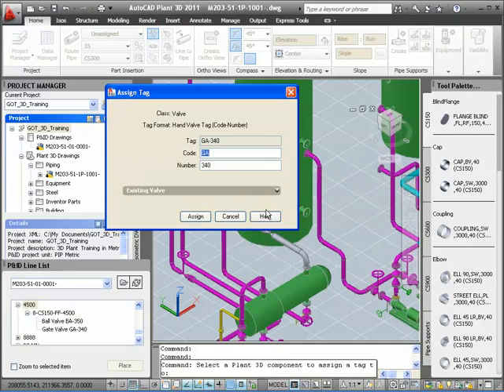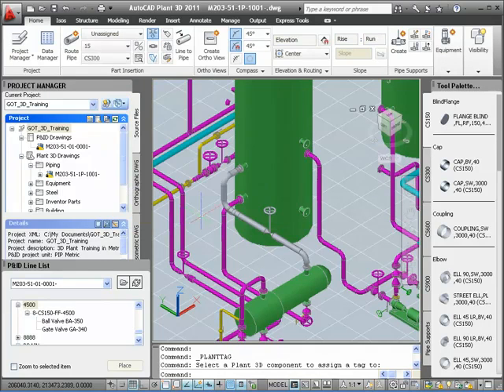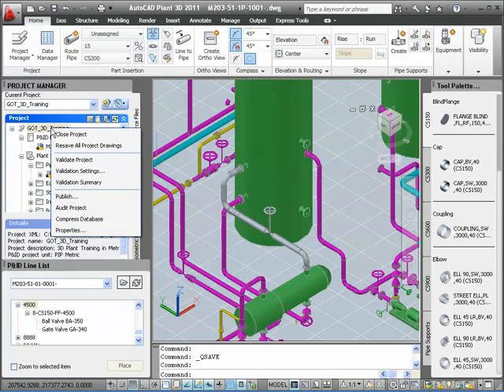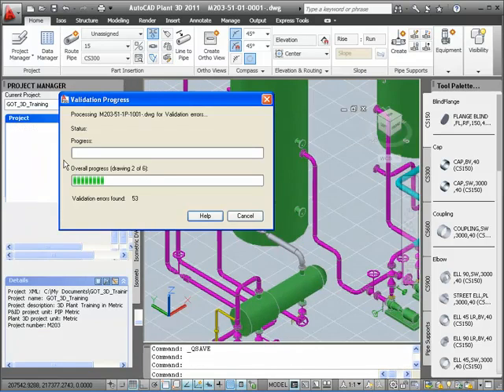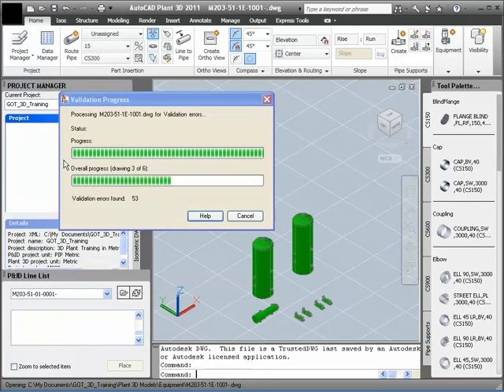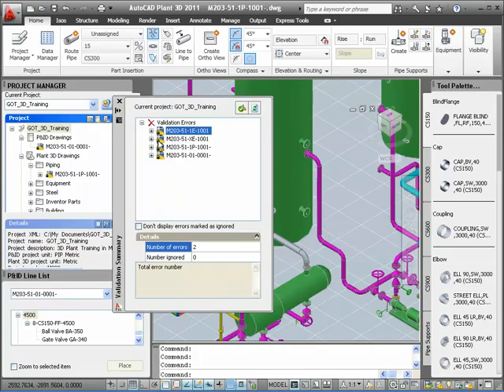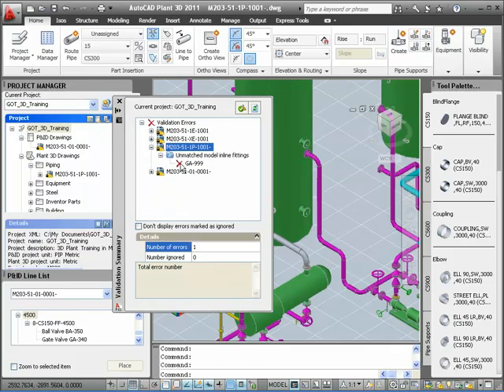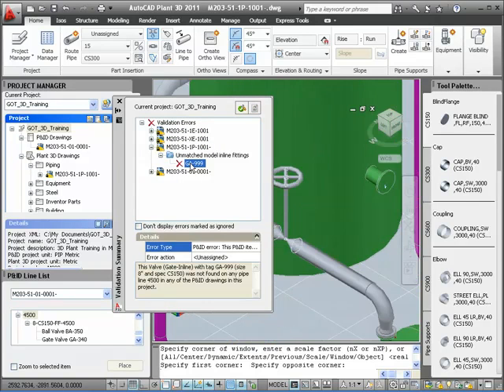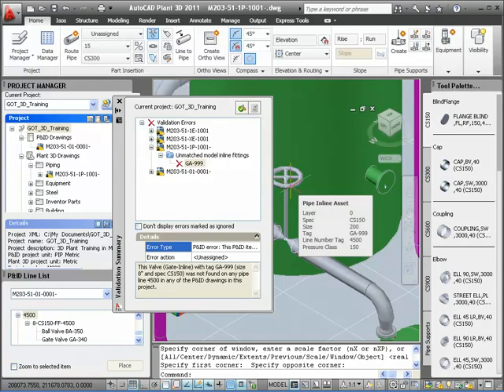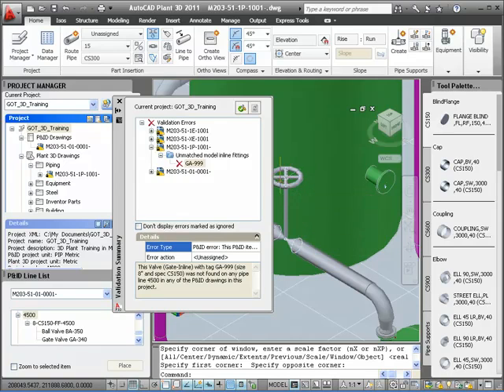Here we go — getting into the tag dialog, changing its number to 999 and pressing Assign. Re-running the validation, we will expect to see the piping model listed with a mismatch. And there it is — we see our piping model listed with a mismatch of model inline fittings. The gate valve tag was not found on the P&ID. To correct this error, all I would have to do is either change the P&ID tag to match the model or vice versa.